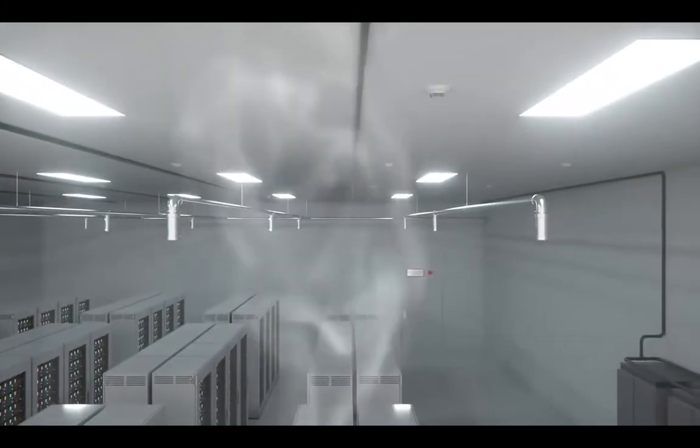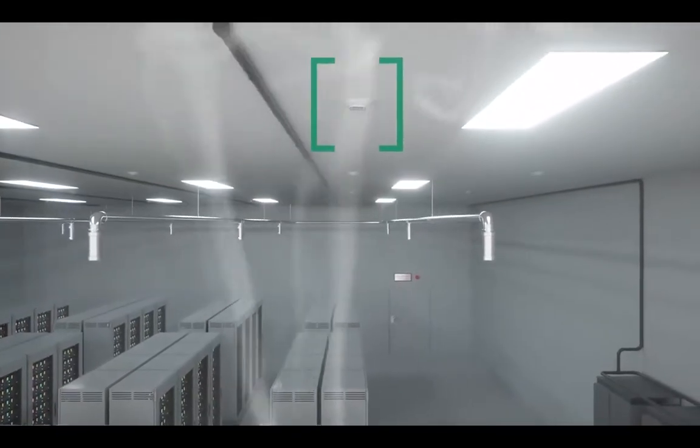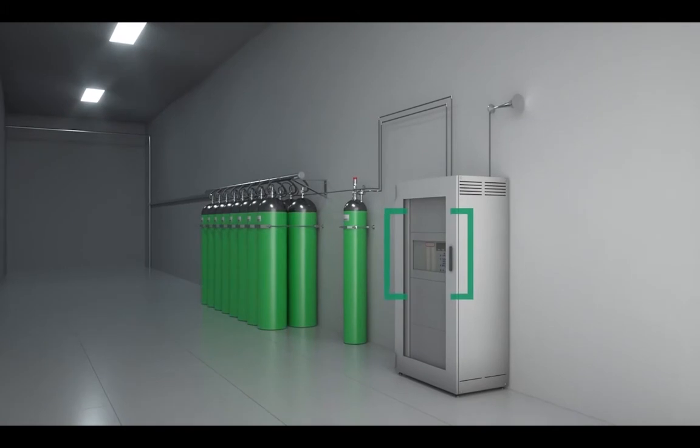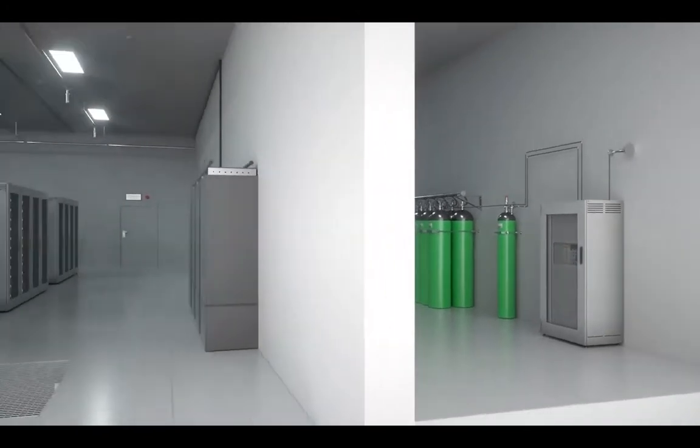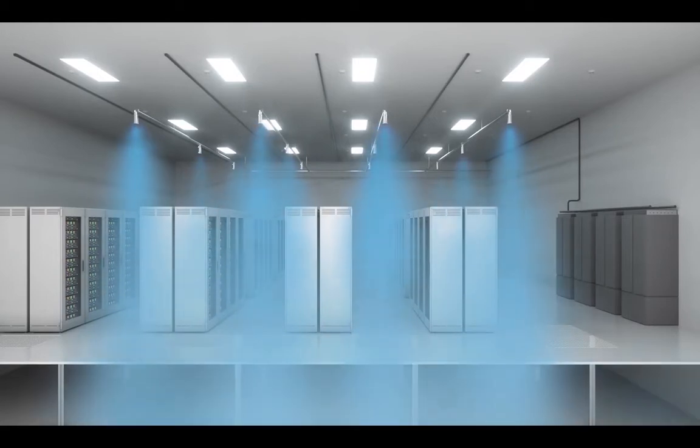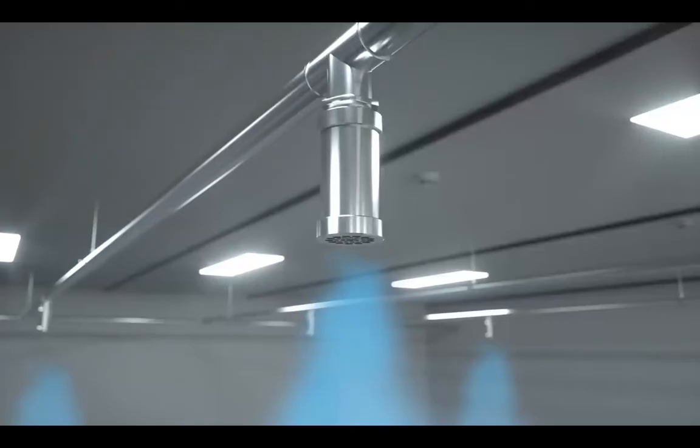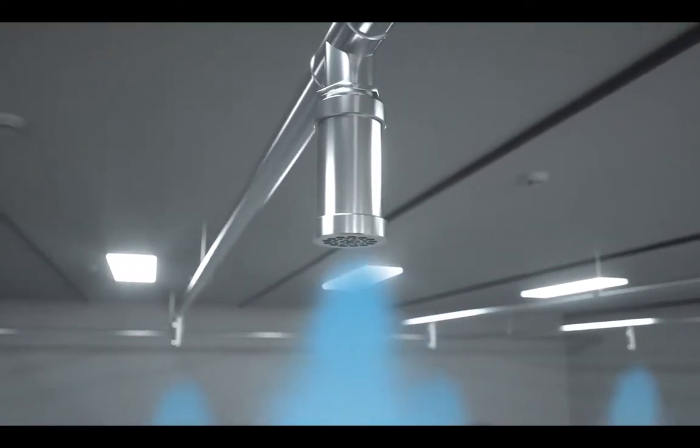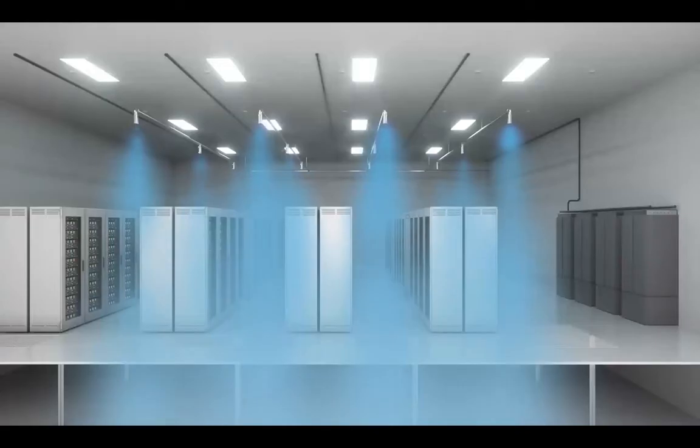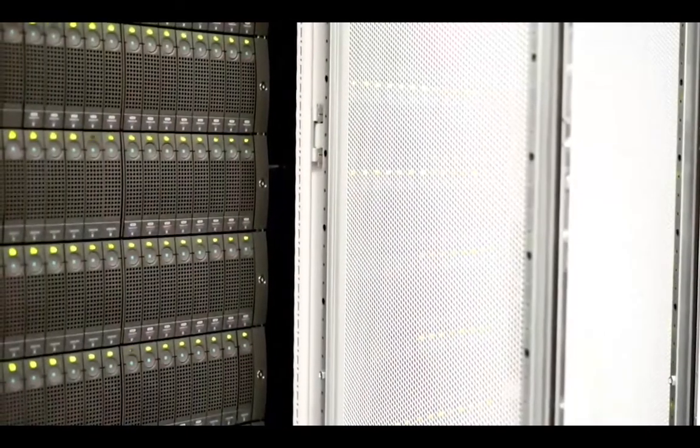If the smoke thickens, point-type smoke detectors trigger the fire alarm. The fire detection control panel actuates the automatic extinguishing system for the area in question. The extinguishing gas nitrogen displaces the oxygen and quickly and efficiently chokes the fire. As nitrogen is non-conducting, no short circuits or chemical reactions occur, and the hardware remains unaffected.